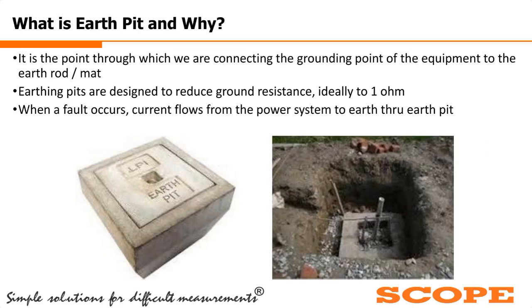An earth pit is a construction in which an earthing rod or any type of earthing plate is inserted into the ground to provide a path for a faulty current. Generally these earth pits are designed to reduce the ground resistance, because an earth pit is an assembly of different components, which are added so that the effective earth or grounding resistance is reduced, ideally below 1 ohm. Whenever a fault occurs, the current will flow from the power system towards the earth through these earth pits.